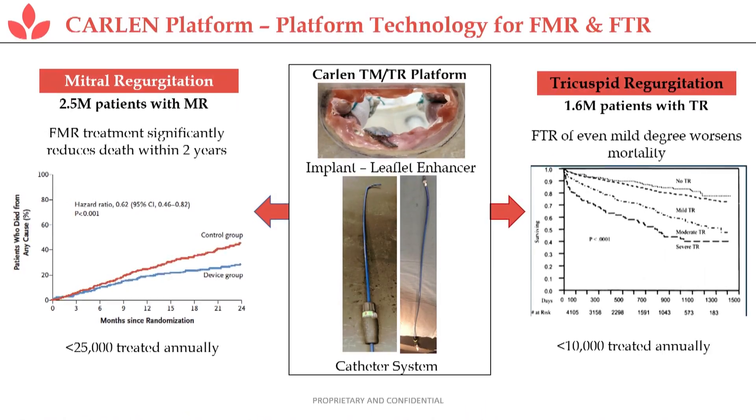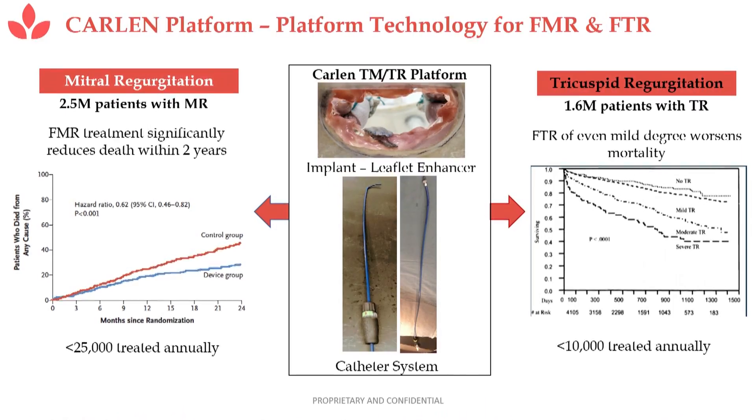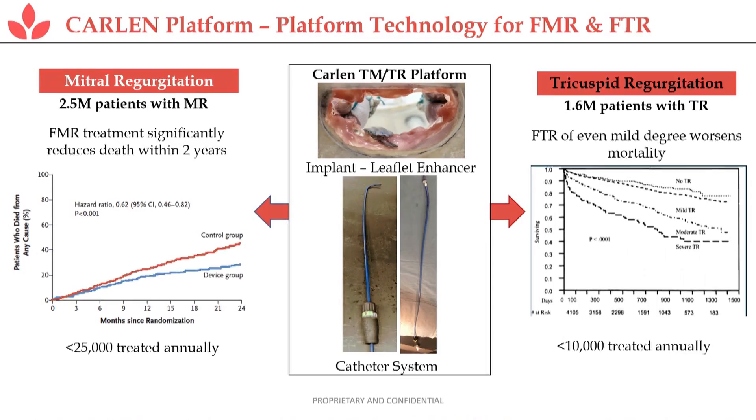Let me talk about what the Carlen platform looks like. In the lower left is a delivery catheter, on the right is a steering catheter, and at the top is an implant. The process we use is a transfemoral delivery of the outer sheath through a transeptal penetration to the area of the valve. The delivery catheter carries the implant to the valve and attaches it to the valve leaflet.